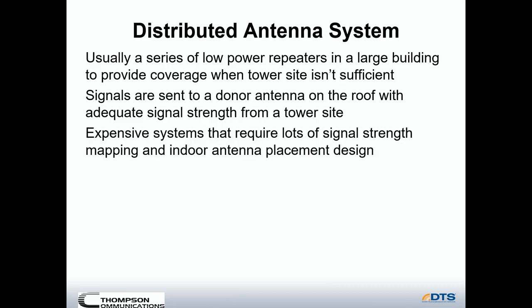DAS systems are expensive. They require extensive signal strength mapping and indoor antenna placement. It's crucial that signals from radios inside the building don't reach the external site as well as get into the DAS system.